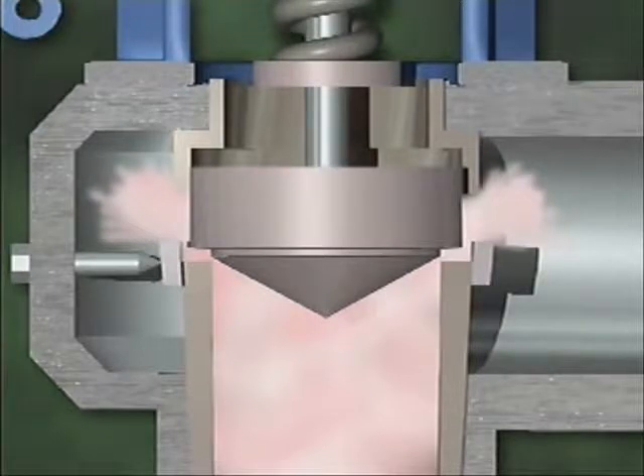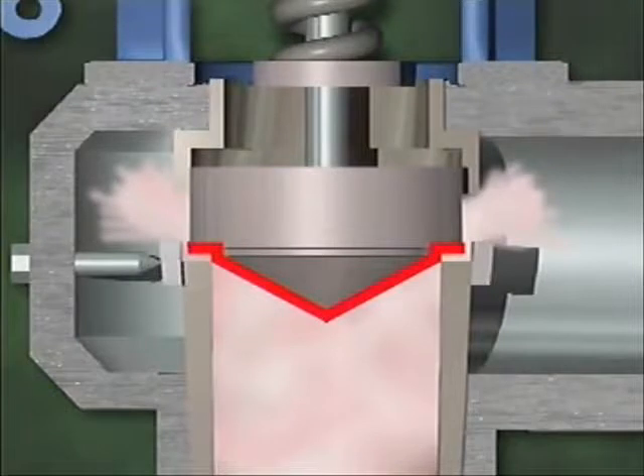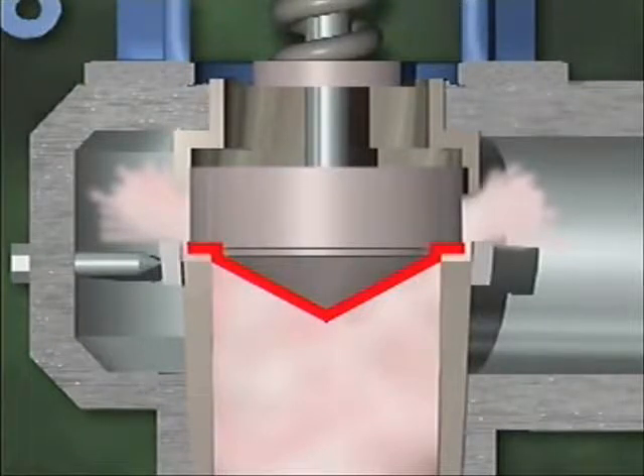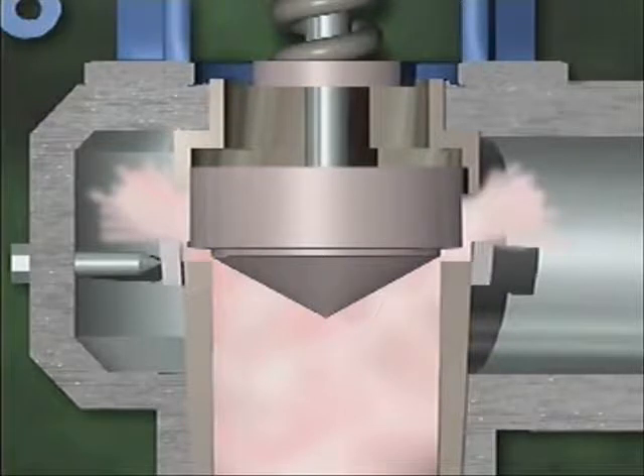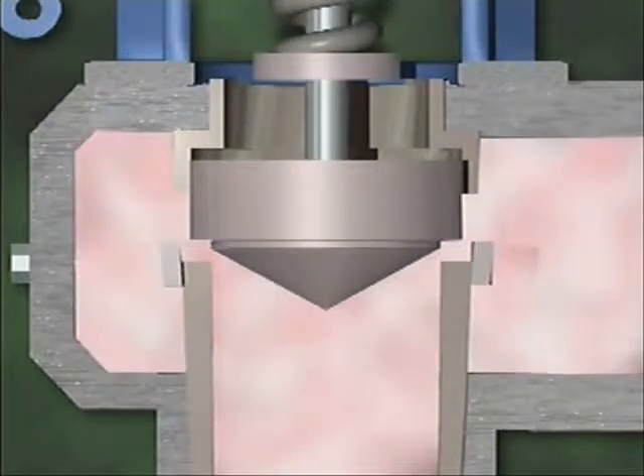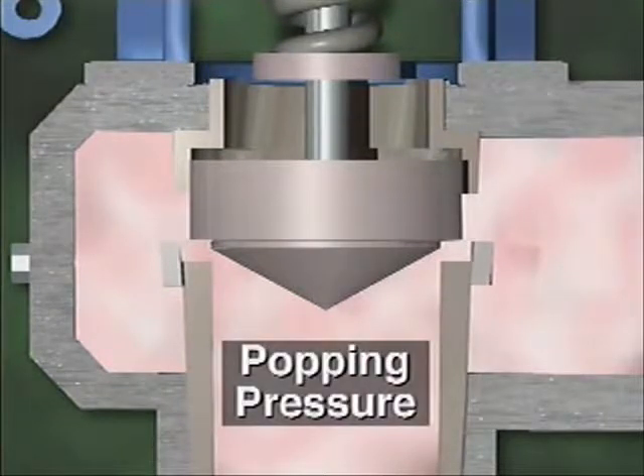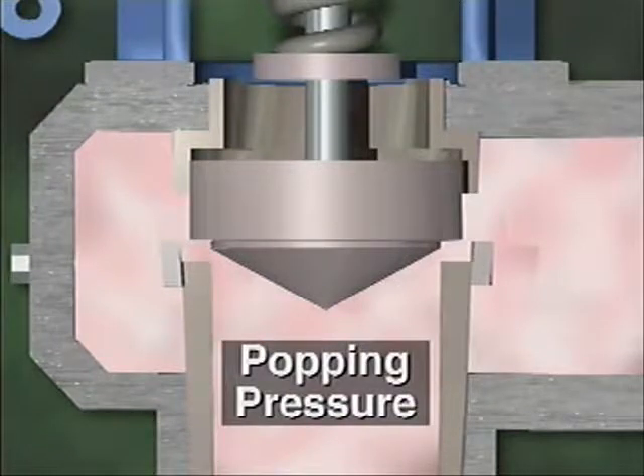As the disc lifts, the lip of the disc is suddenly exposed to system pressure. Since a larger area of the disc is now exposed to pressure, more force is being exerted on the bottom of the disc. This increased force overcomes the spring tension and causes the disc to pop open to about a 60% open position. When the valve's popping pressure is reached, the valve should open with a clean and sudden pop.